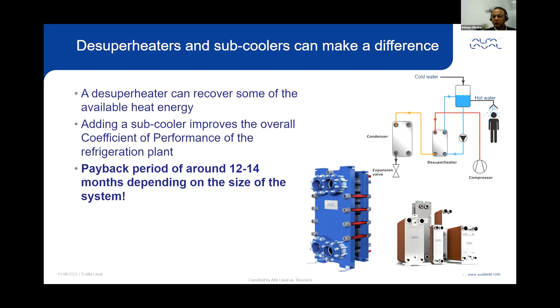After the compressor, the hot refrigerant can be cooled in a desuperheater and thus recover some of this heat energy. This heat can be used to produce hot water, which can be used for various purposes in the plant. Further, adding a subcooler can help improve the overall coefficient of performance of the ref plant. So we have a range of very efficient, compact, brazed plate and semi-welded heat exchangers that can enable this. And the payback period is less than 12 to 14 months, depending on the size of the system.